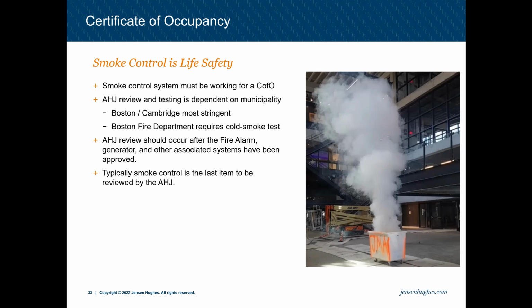But showing that the system does exhaust smoke, this cold smoke test is not intended to be something that demonstrates the smoke control system's capacity. So it's not intended to show that the system can exhaust a fire, just that smoke is moving out. Some municipalities, I've seen other ones, will also require this at some point. But most of the review is contingent on that CFD analysis that Tony talked about earlier. And there actually is language in NFPA 92, which is a standard for smoke control systems, that talks about not using smoke to demonstrate the system's capacity, because obviously cold smoke has different properties than smoke from a fire, which is going to move up much faster.